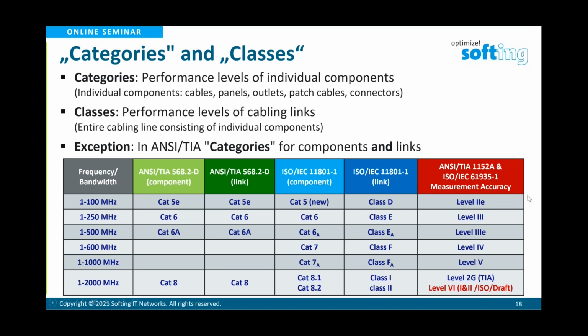So people sometimes get a little confused about the difference between international and European standards - ISO IEC 11801 and following - which name all links in classes, class D up to class 2, versus the Americas, which have links classified from category 5E up to category 8, but without category 7 and 7A, since the Americans didn't want to use those.